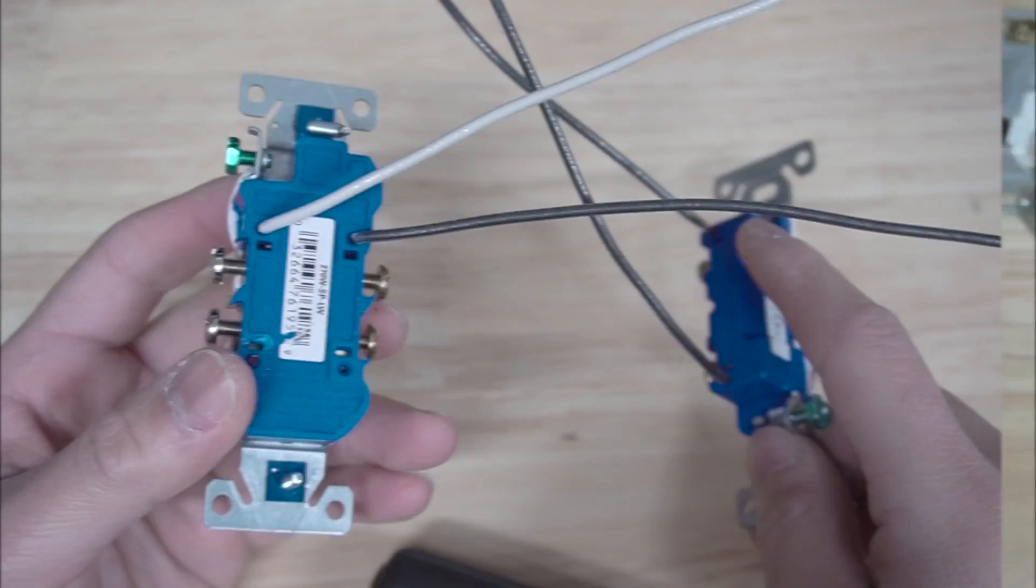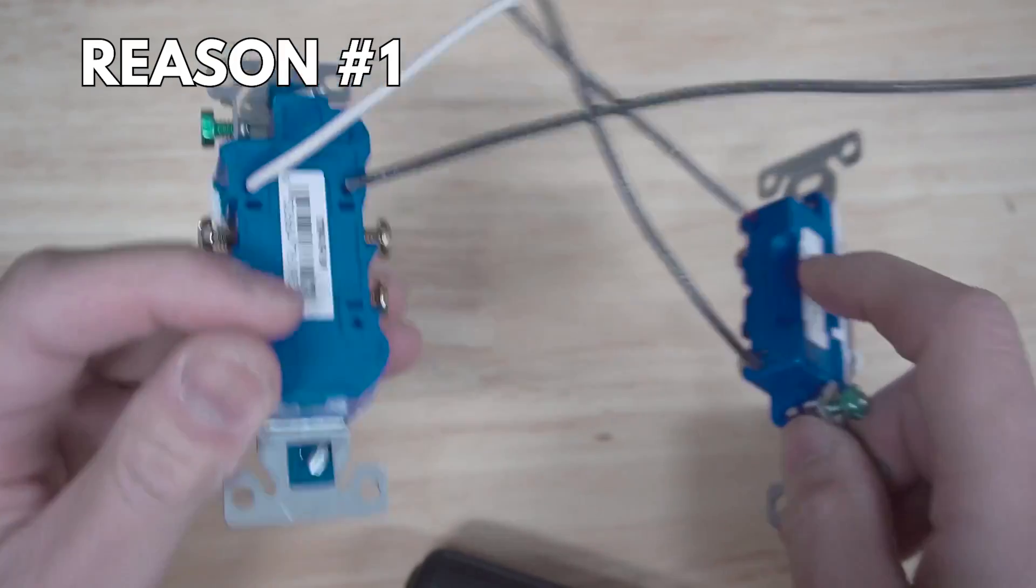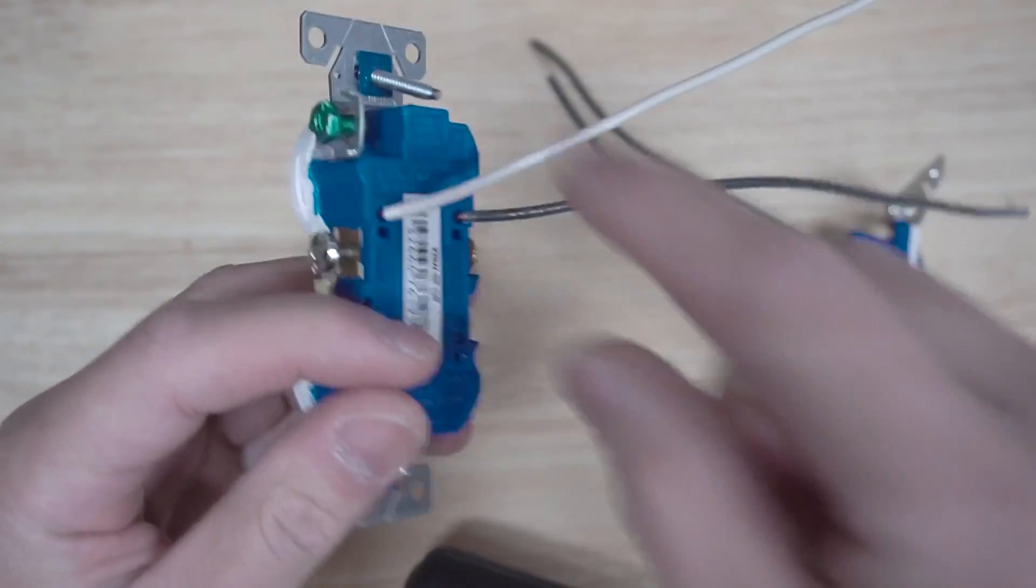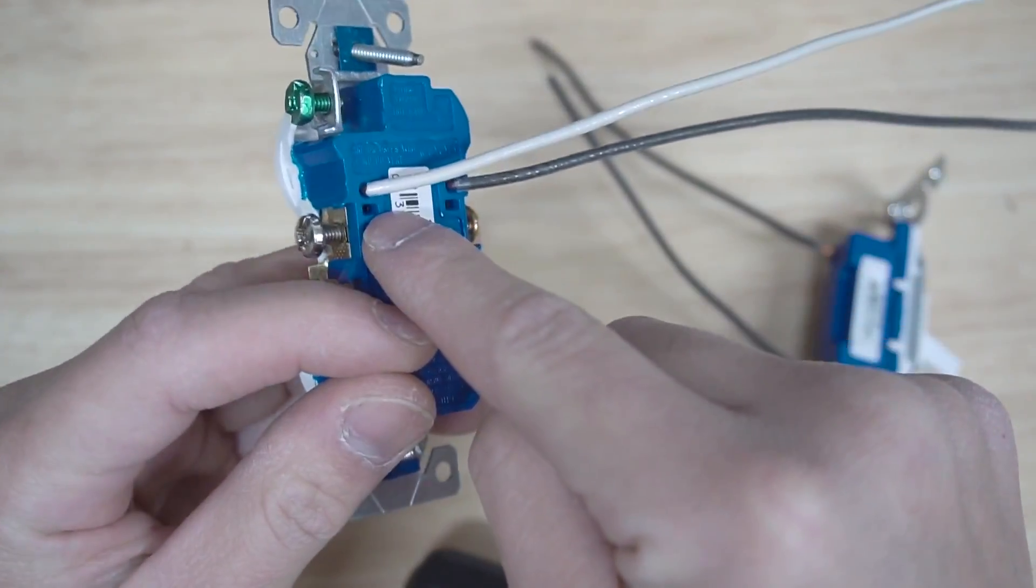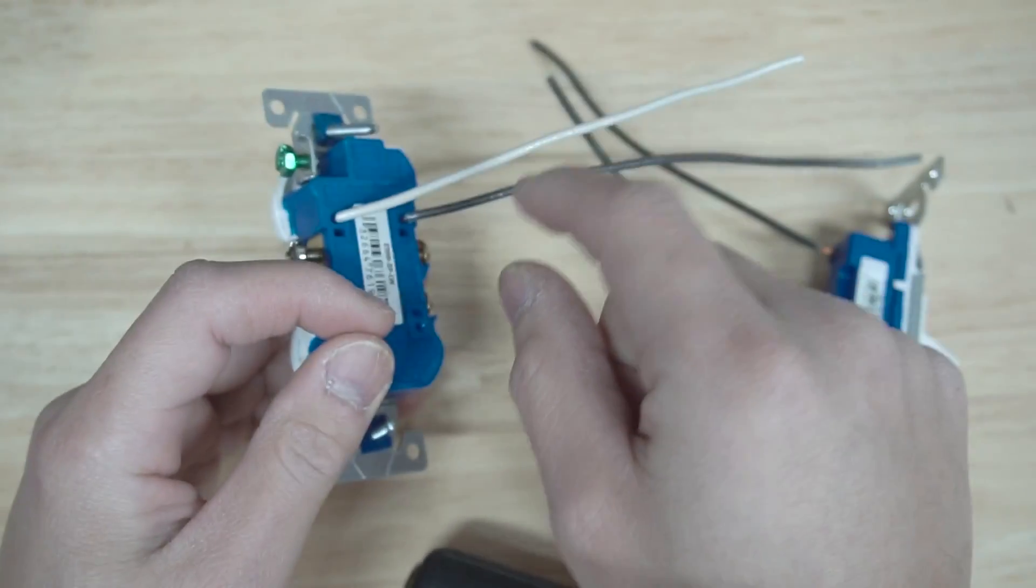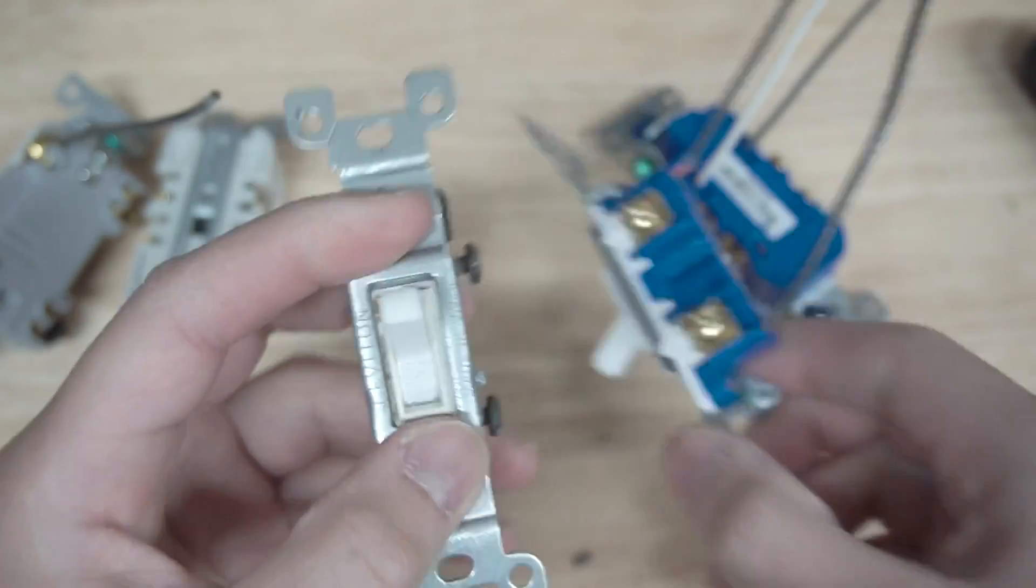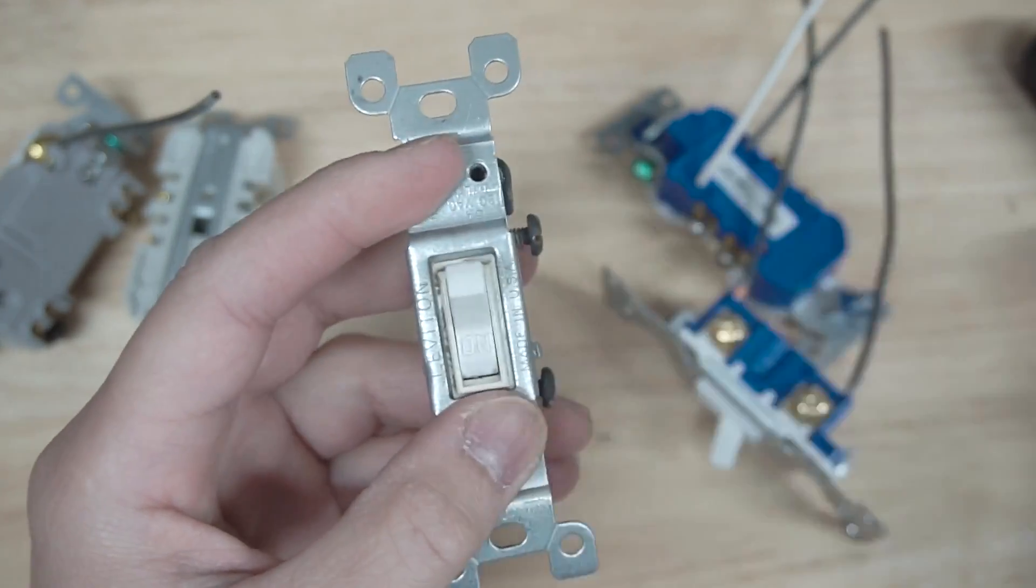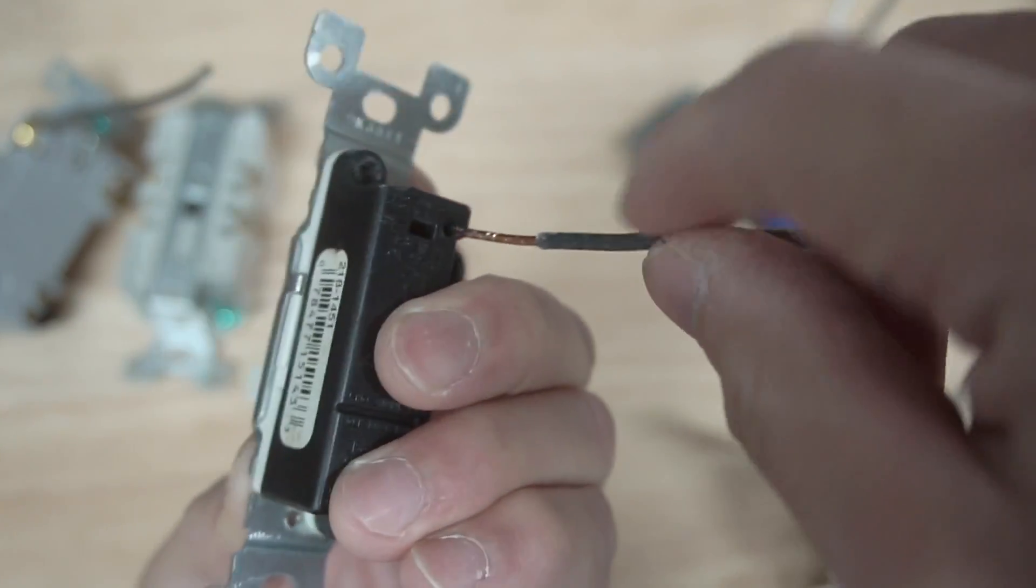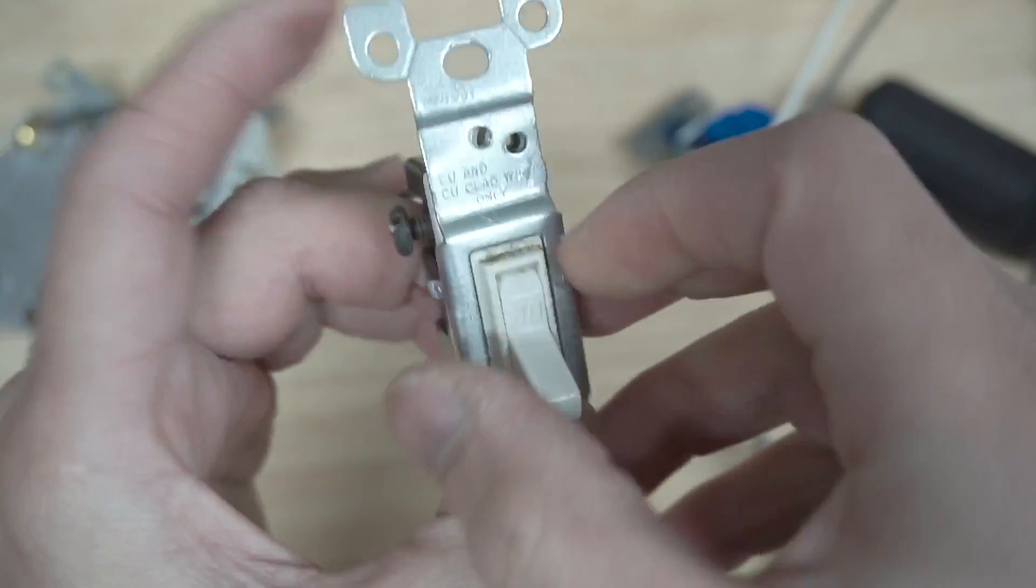Reason number one why you shouldn't backstab, back wire, or use these push-in terminals is because there are less contact points when you do this method. If you push this into the push-in terminal, I will show you later on why there's a little bit of contact from the terminal with the wire. Let's push this in on this speed wire terminal, and if you open it up...